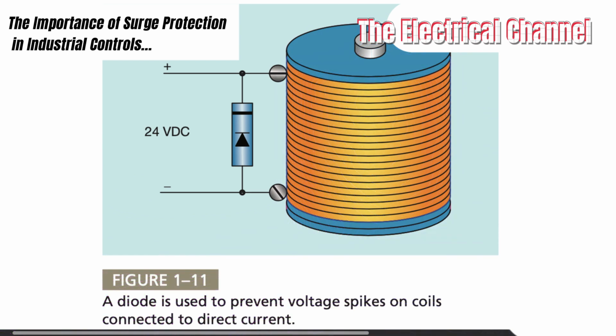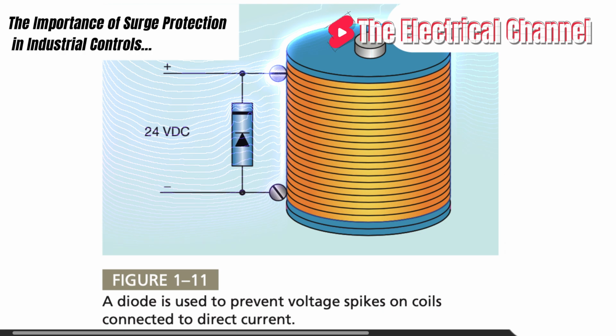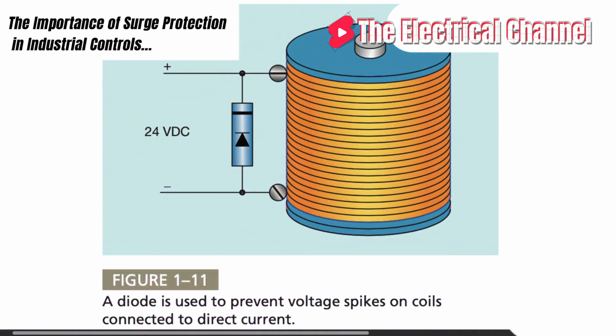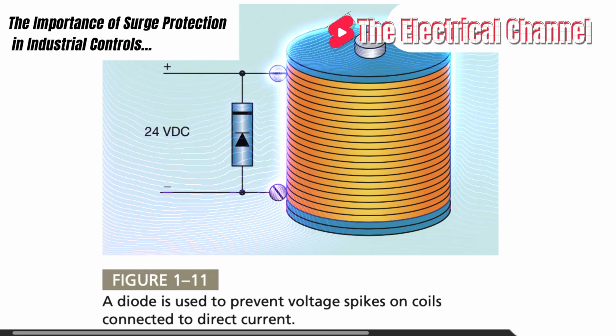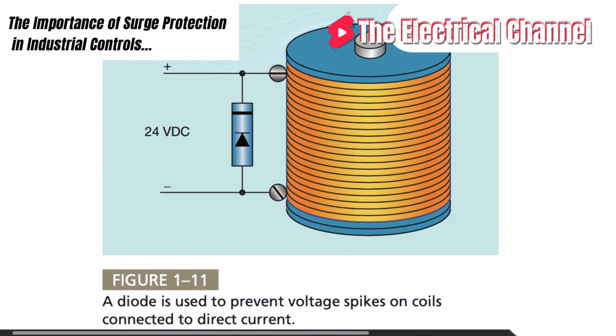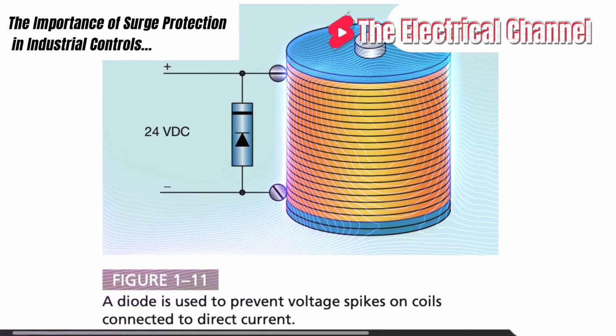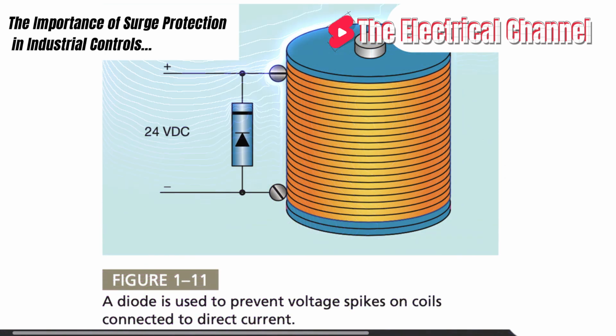Today we're going to talk about surge protection. Another concern in many control circuits is the voltage spikes or surges produced by collapsing magnetic fields when power to the coil, relay, or contactors is turned off. These collapsing magnetic fields can introduce voltage spikes that are hundreds of volts.